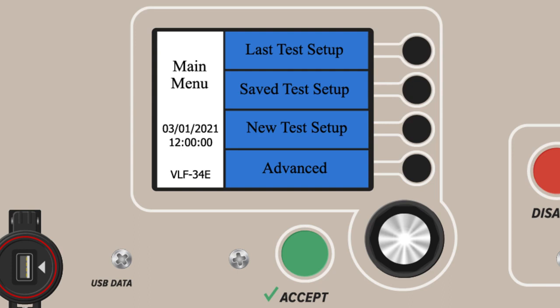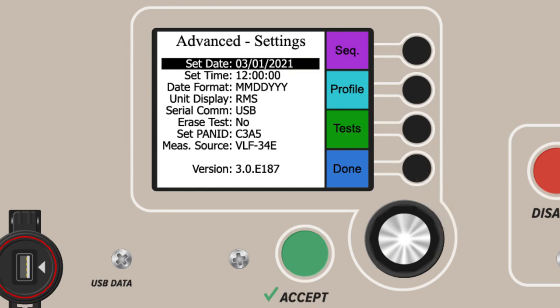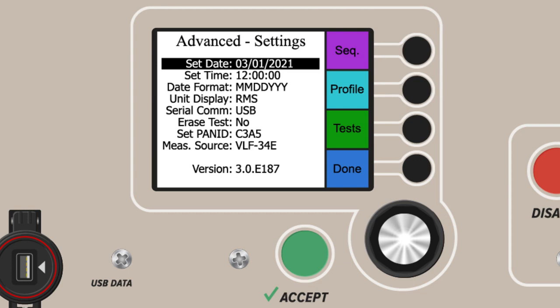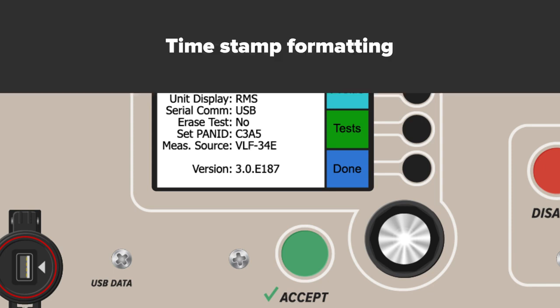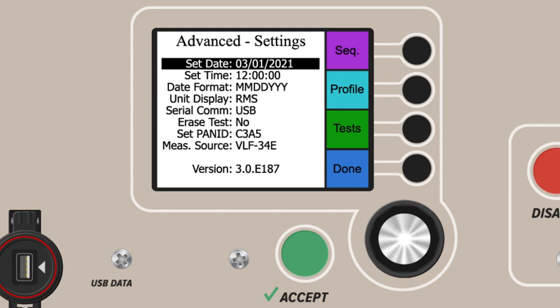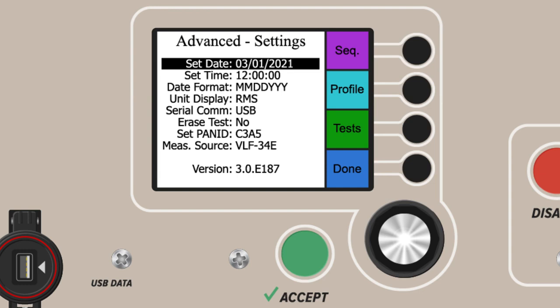The fourth and final option from the main menu is Advanced Settings. From here, users can fully create, view, edit, or rename saved testing profiles and sequences. All saved files on the device can be copied, moved, or deleted. The advanced settings also control date and time settings and formatting. All tests are time-stamped, so proper date formatting is important. The advanced settings also control the units displayed for voltage, RMS or peak voltage. Advanced settings also display the current measurement source and have a PAN ID selector for connecting to E-Link software and to external devices such as a Tan Delta bridge. Finally, advanced settings is where your firmware version is displayed.